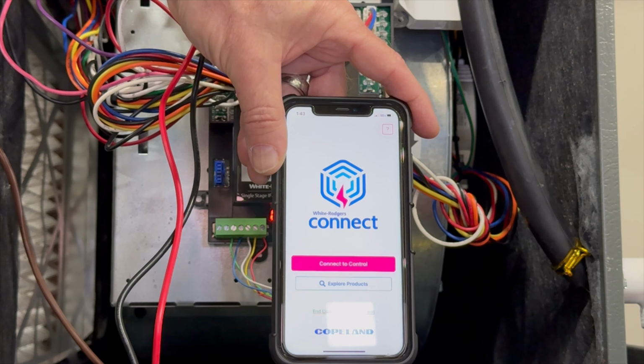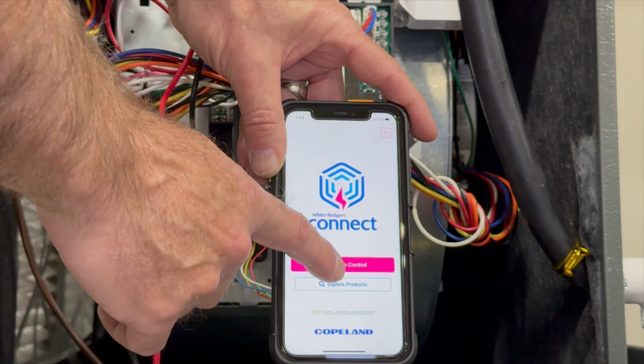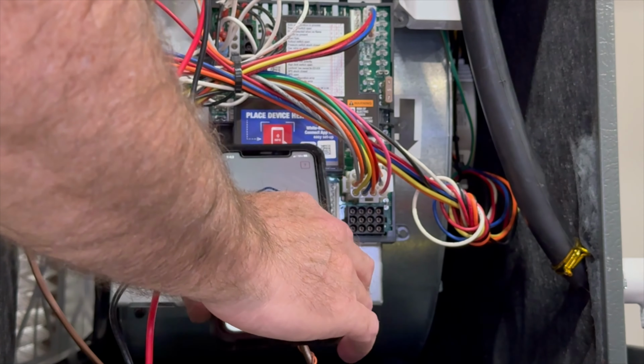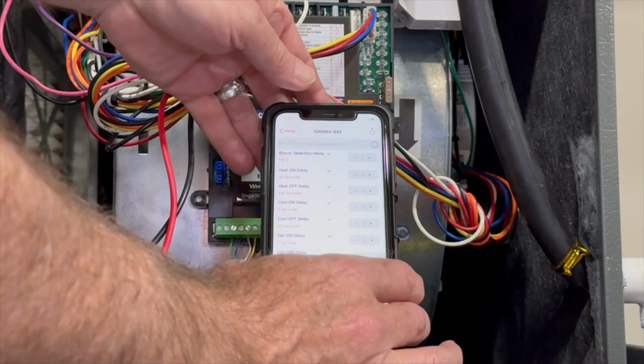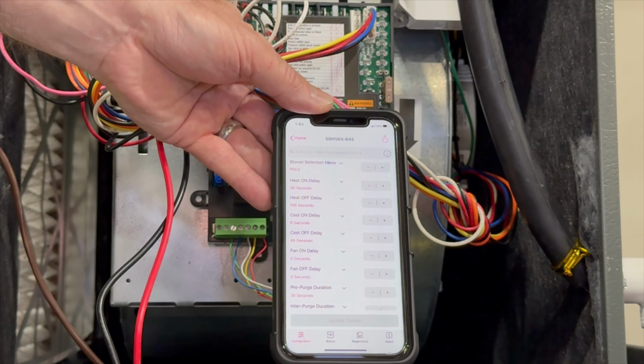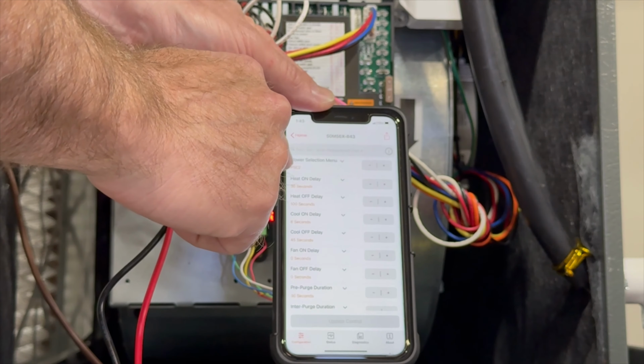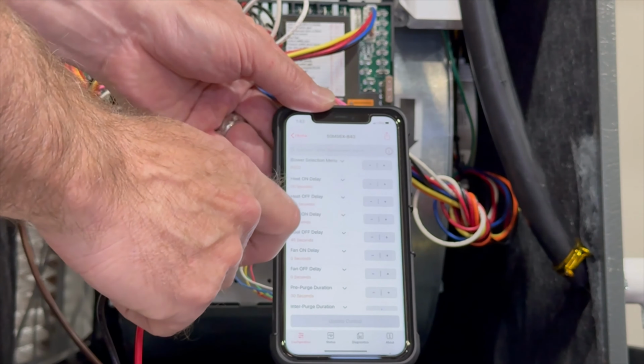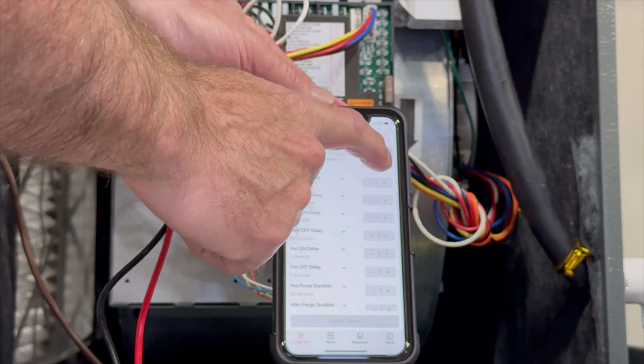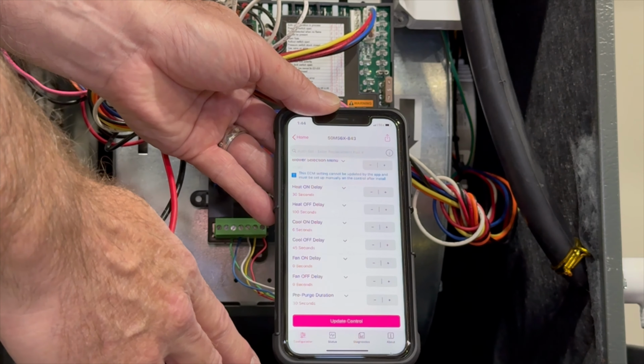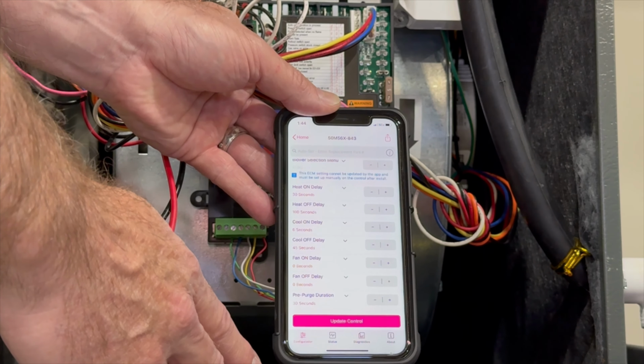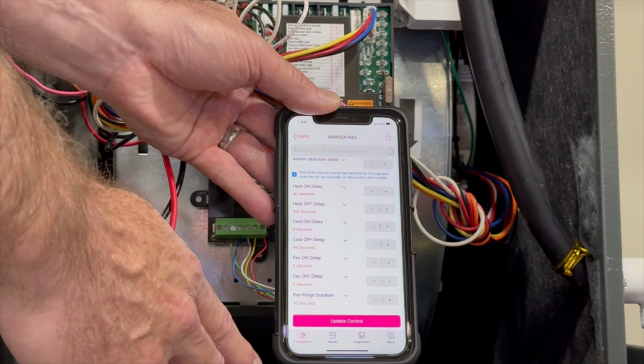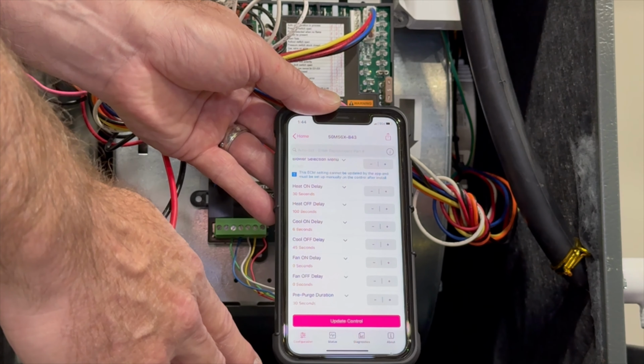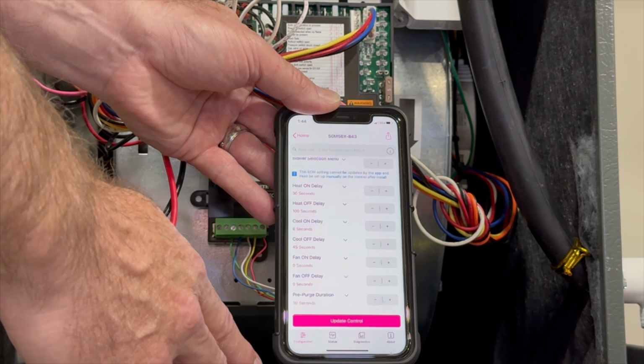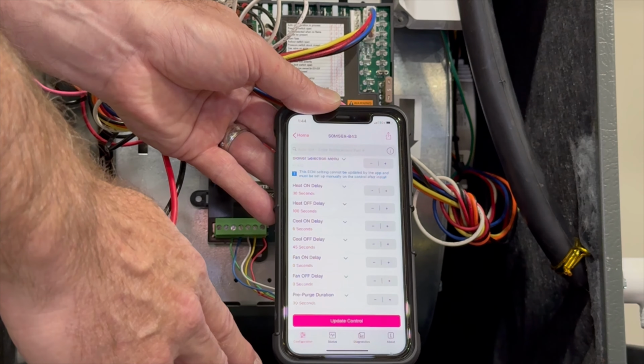Once the board has been installed, go into the White-Rodgers Connect app, tap Connect to Control, and then hold the phone over the control where it will read the device. So the top edge is right in the middle there. Once you actually have the control, the top menu item is going to be Blower Select, and it's currently set on PSC2. So if you hit the plus button, you will switch through PSC2 to PSC3 to ECM. Once you get past PSC2 and PSC3, which are for permanent split capacitor motors, you will get a notification sharing that this ECM setting cannot be updated by the app and must be set up manually on the control after installed, which means this is something that will be manually set up in the control to go to the ECM type of blower. So we will do that right now.